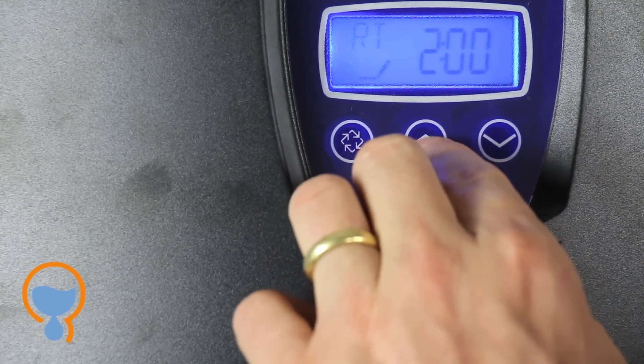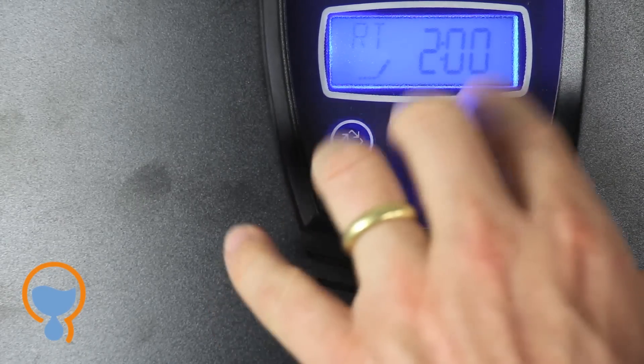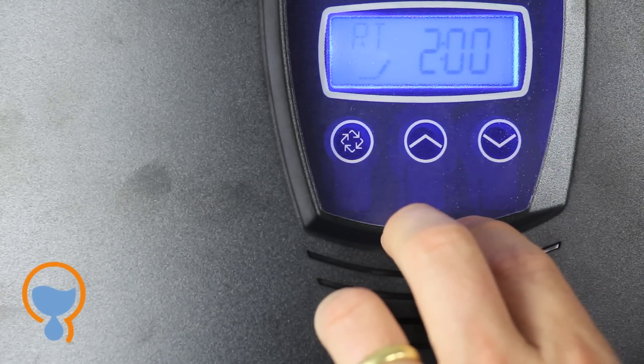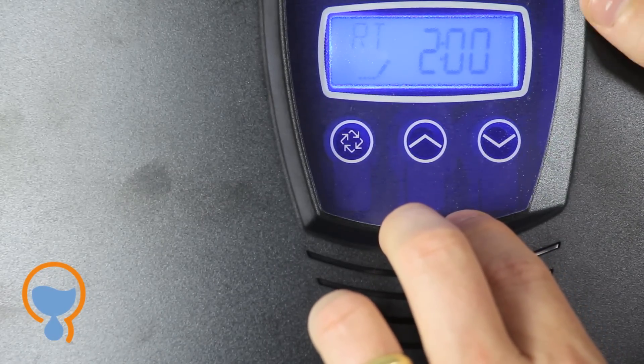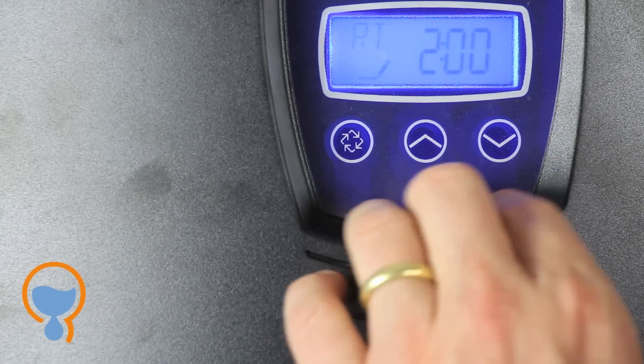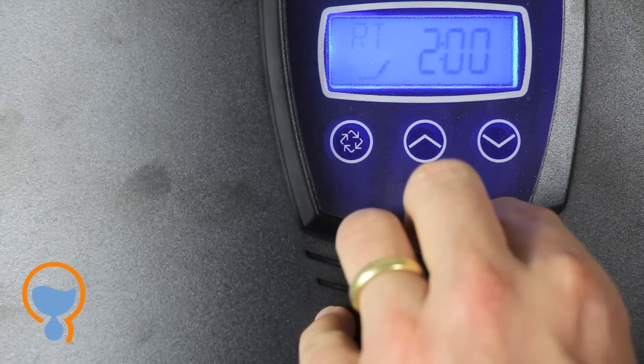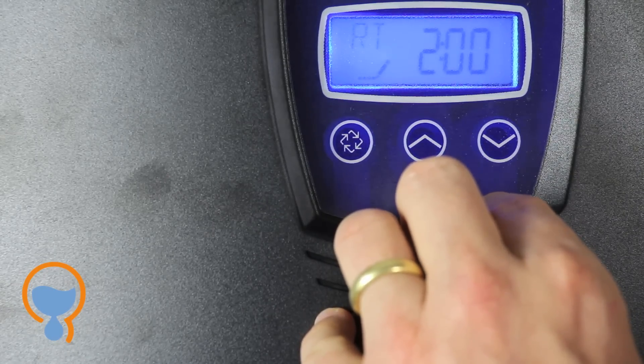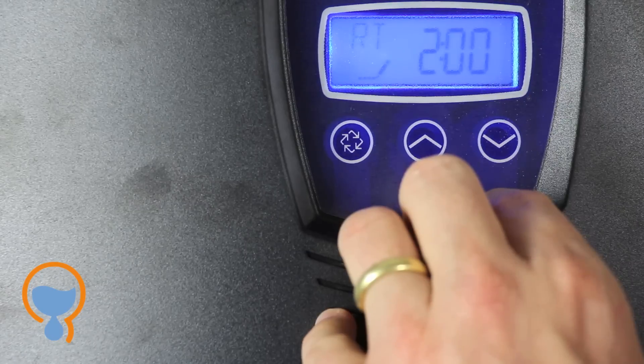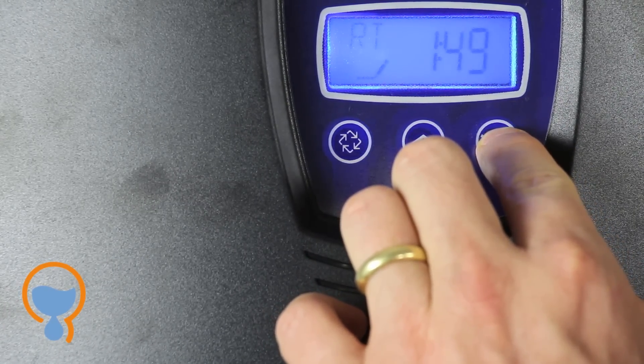Regeneration time. You can choose any time you like for the softener to regenerate. The Fleck 7000 SXT in the way we're setting it up here is in the meter delayed configuration. So it will only regenerate at the time that you say on the day that it needs to regenerate. Lots of people, 2 AM is the ideal time in the middle of the night. That's what this control valve defaults to. Sometimes for families who are out of the house all day, 2 PM isn't a bad time either. So why don't we set this to 2 PM in this case.